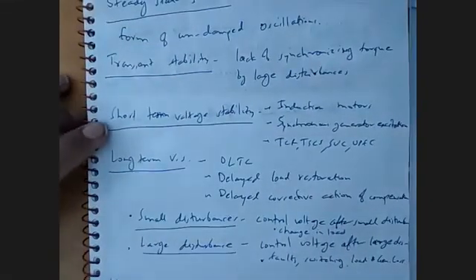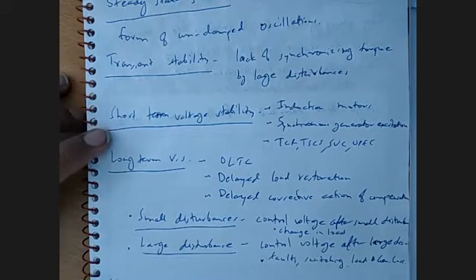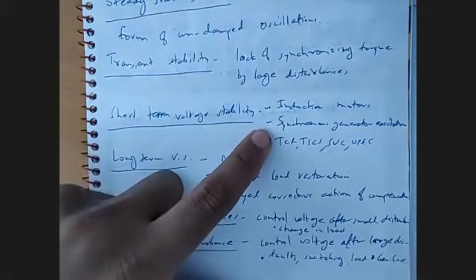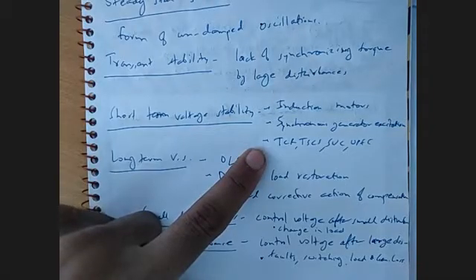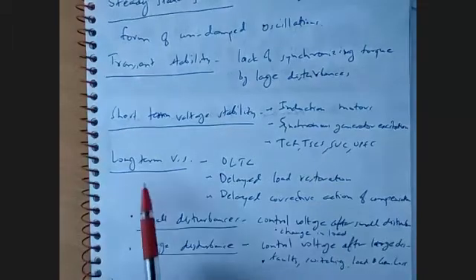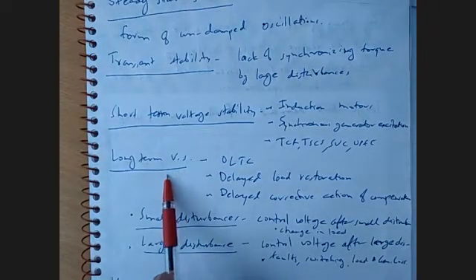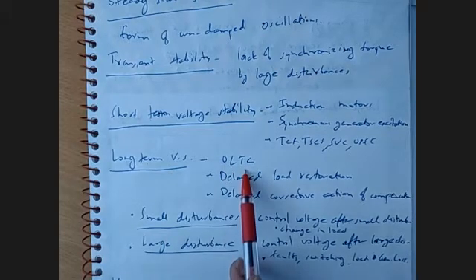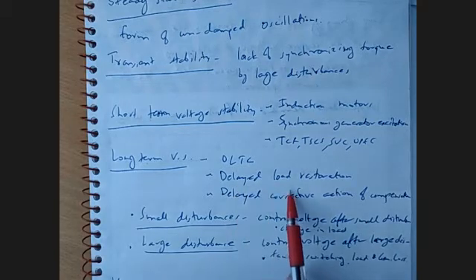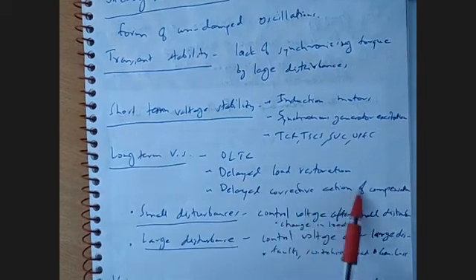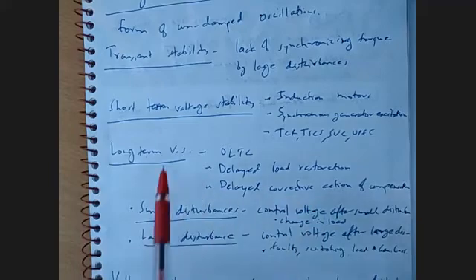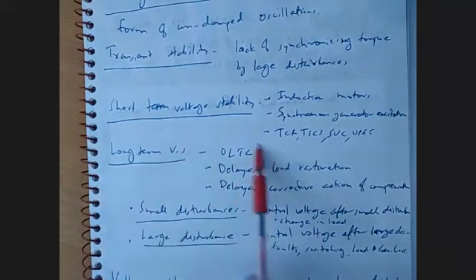And then if we are talking about load disturbances, we have short-term voltage stability. Short-term is for a small duration, and it may be due to the operation of induction motors, or due to the excitation system of synchronous generators, or due to the operation of various compensating devices like TCR, TSC, SVC, or UPFC. And when we are talking about long-term voltage stability, it is due to the operation of OLTC, tap settings of transformers, delayed action in load restoration, and delayed operation in corrective action of compensating devices in the system. So long-term voltage stability is due to these parameters.